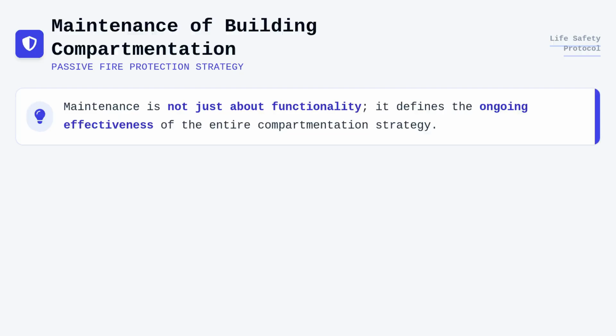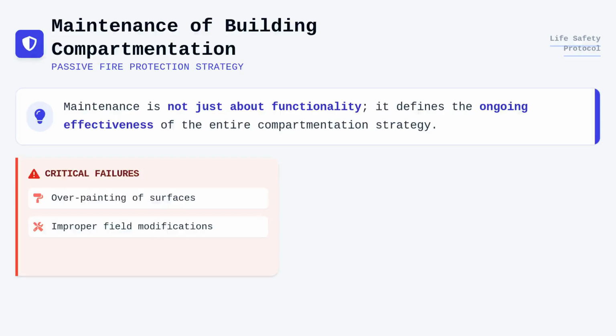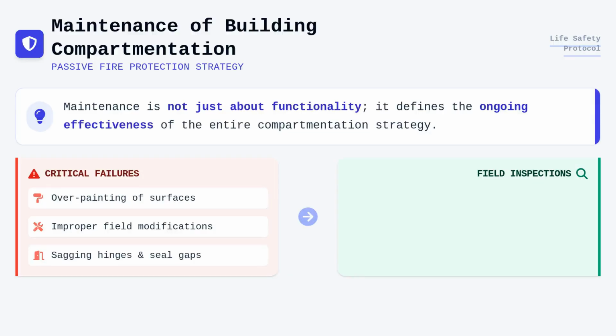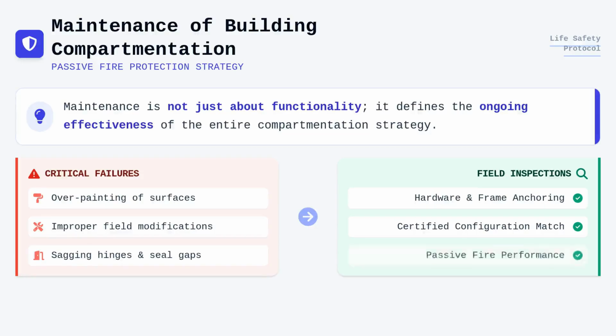We often see issues where overpainting, improper field modifications, or sagging hinges compromise the assembly's ability to seal against smoke and flames. Field inspections serve as a final check to ensure that the assembly, in its installed state, matches the certified configuration tested in the laboratory. By scrutinizing the hardware, frame anchoring, and the door itself, we ensure that the passive fire protection system continues to provide the necessary life safety performance.